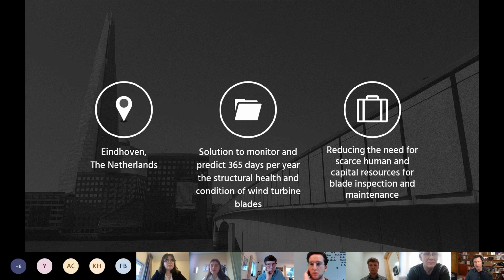That's a big issue. Another issue is the dielectric strength of the plastic material, the fiberglass and epoxy, over time. What Peter's measurements are finding is that blades are constantly exposed to lightning or charge almost all the time, particularly in summer months in the United States — pretty much every day exposed to massive amounts of charge. That weakens the electric structure of the blade. We think of the blade as massively strong, and it still is mechanically, but electrically, not so much. So as blades age, that adds another problem.